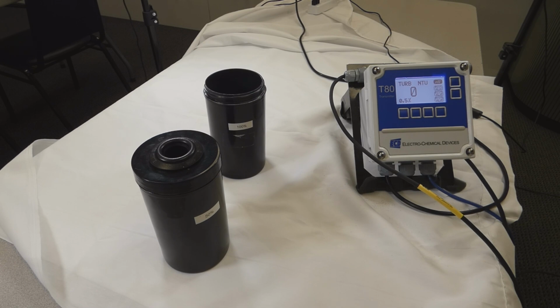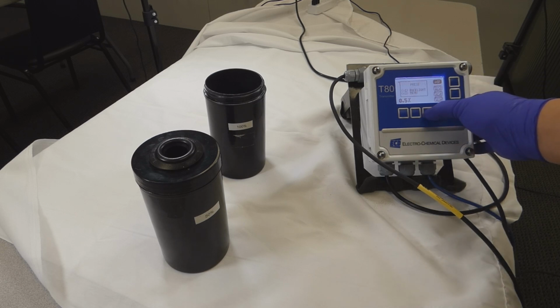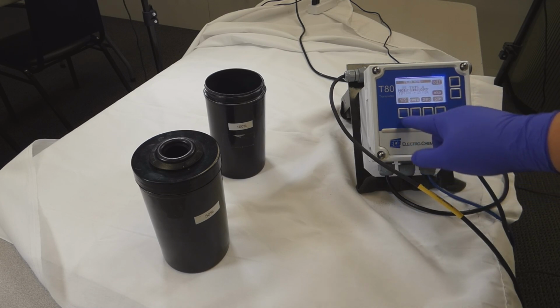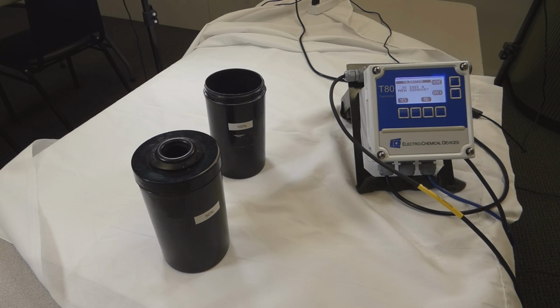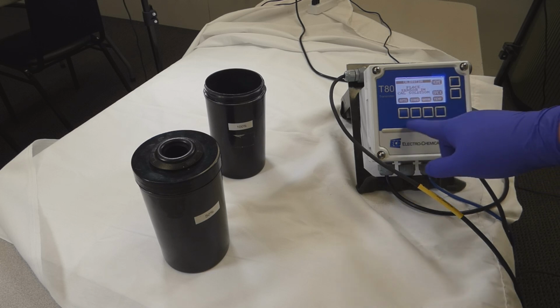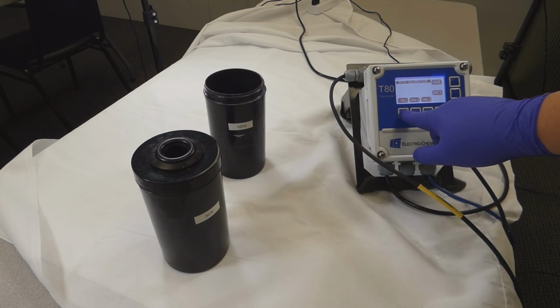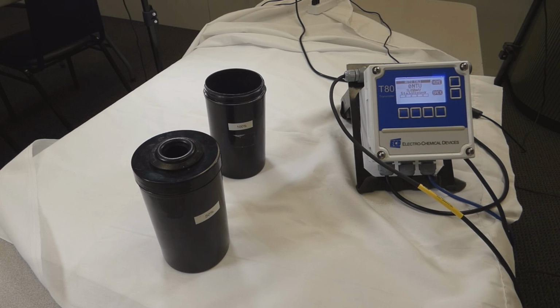So in order to get into the first calibration, you'll press any of the bottom 4 keys twice. You'll press Cal. It will ask you if this is a new sensor. If this is a new installation or a replacement sensor, you will press yes. Any other case, you just say no. By pressing yes, what you're doing is erasing all of the calibration storage data in the sensor. You'll press Auto, Cal 1, and wait for the stabilization bar to finish.